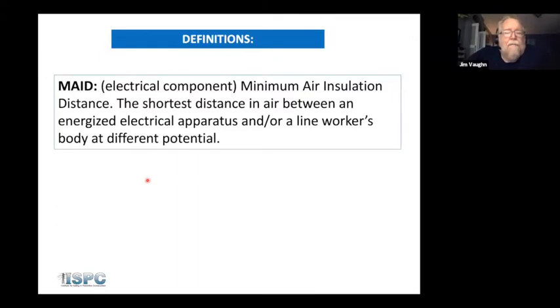If I have a fastened conductor on a pole top, and I bring a ground into it, when I get almost to that MAID, it's going to flash to ground. And just like a man being up next to that, and especially a grounded man, this conductor will arc over, and that's the MAID distance.